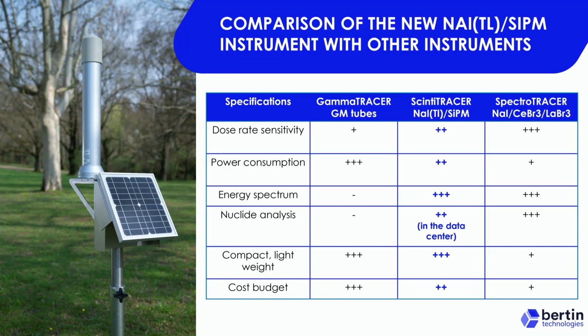So what was the idea of our ScintiTRACER? The idea was to combine the best of a dose rate probe with the best of a spectrometry probe. For sure, dose rate sensitivity with a Geiger-Müller device is not as high as with a scintillator, a NaI, lanthanum bromide, or whatever. Power consumption is a very important point when you think about infrastructure. The GM tubes do not need as high power as a real spectrometric probe.